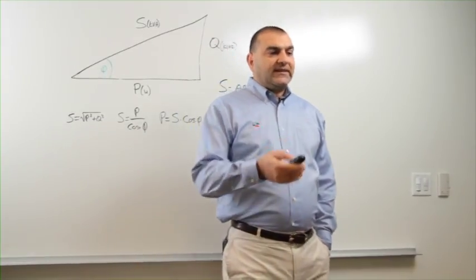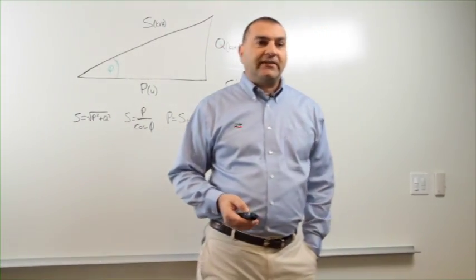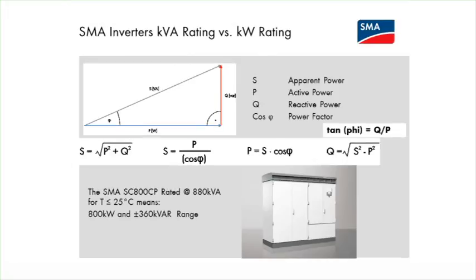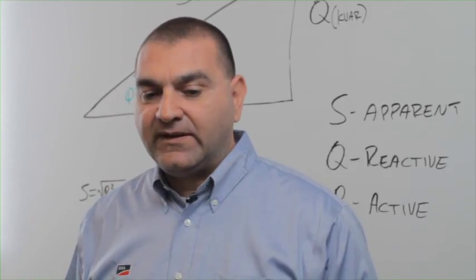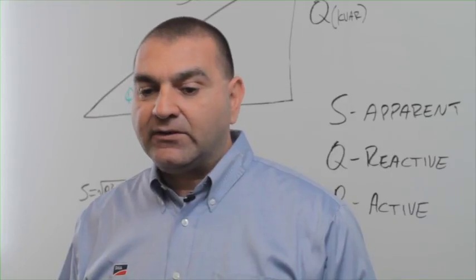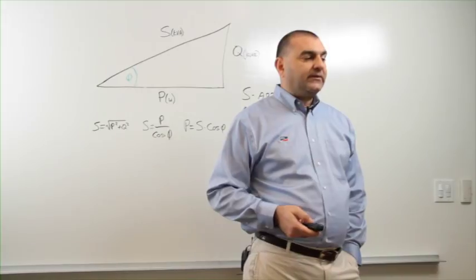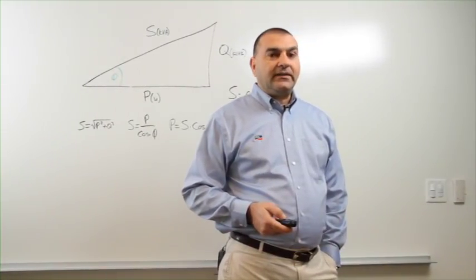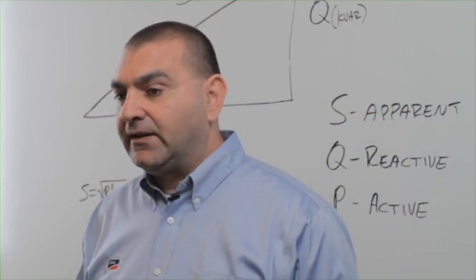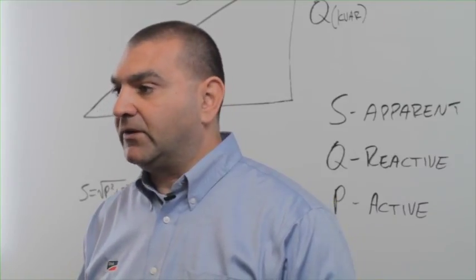All right, so in order to facilitate the understanding to the utility that are normally used to rating the facility in MVA versus megawatts or kilowatts, SMA started also rating its inverter in kVA. So in this particular example, the relationship of apparent power, reactive power, and active power is shown in what we call the Pythagorean theorem, and that's just trigonometry, in which case the apparent power, which is normally referred to as S, is equal to the square root of active power P squared plus reactive power Q squared. So for example, the SC800CP, which is rated 800 kilowatt, is also rated 880 kVA for temperatures of less than or equal to 25 degrees Celsius. What that means to the developer and the utility that are used to facility rating in kVA is that this inverter is capable of 800 kilowatt, but also it can provide a range of 360 kilovar, lagging or leading, plus or minus 360 kilovar for that particular inverter type.